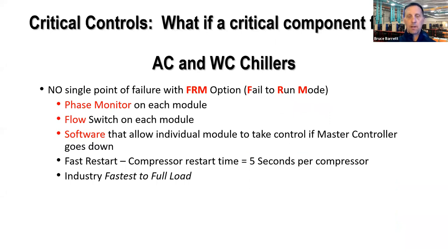One component of our modular and water-cooled chiller line is establishing no single point of failure. And we've got an option that we call FRM, or fail to run mode. When we have those critical jobs, we don't rely upon a single chiller's phase monitor. If that phase monitor is fickle, that can take the entire chiller down. It's a $150 part or less. A singular flow switch on a chiller, if that's funky, that can take your entire chiller down. If a lightning strike or a voltage surge rips through your transformer, that can take your master controller out.